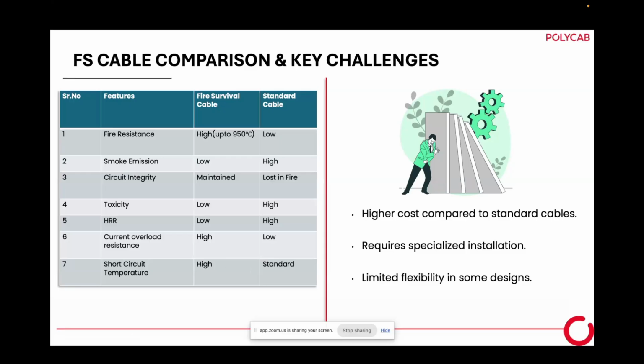Higher cost. Fire survival cable always has a higher cost because the technology is costly. It requires some specialized installation, with limited flexibility in some designs. You cannot bend it too much because the moment you bend, the mica tape will get affected. So we recommend that bending should not be much. It should be in a fixed installation process.